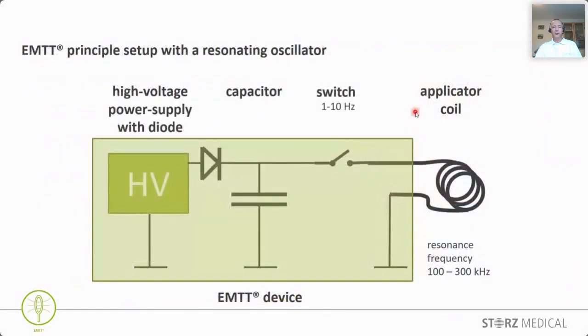So what we do with these systems, we use a resonating oscillator. With this sketch, you see the principle of how it's really done. Within the EMTT device, you have a high voltage source, you have a capacitor which is charged, and then with a switch that is opened up to 10 times per second, you discharge the capacitor over the coil. And here you get this kind of resonance going on between the capacitor and the coil, because the current is flowing from one side to the other until the energy is gone. This resonance frequency could be chosen here with 100 to 300 kilohertz by doing this.